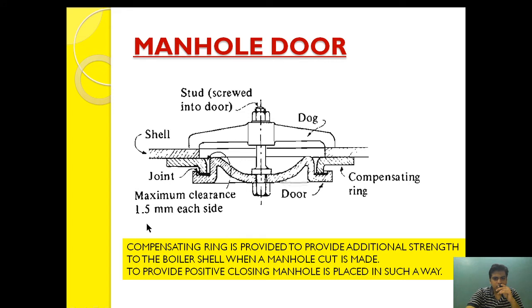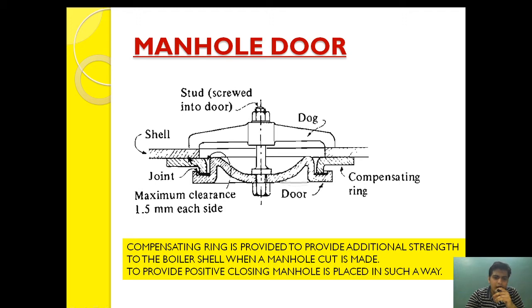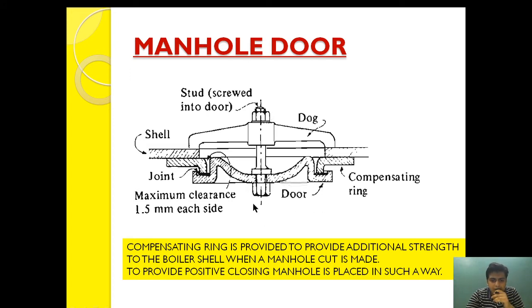For that reason, a compensating ring is provided in a manhole door, which is welded. As you can see, this is the inside of the boiler and this is the outside. The compensating ring is cut here. Now, the second thing is this is the manhole door, these are the long nut studs, and this is the dog nut which is holding the manhole. As the door is elliptical, to ensure positive closing, it is closed from the inside direction so that the pressure building up also helps the positive closing of the manhole door.